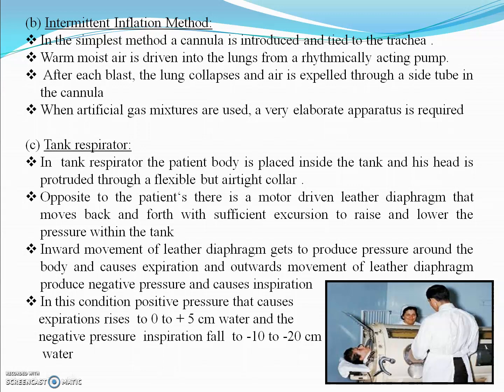Next is the tank respirator. In the tank respirator, the patient's body is placed inside the tank and his head protrudes through a flexible but airtight collar. Opposite the patient, there is a motor-driven leather diaphragm that moves back and forth with sufficient excursion to raise and lower the pressure within the tank. Inward movement of the leather diaphragm produces positive pressure around the body and causes expiration. Outward movement of the leather diaphragm produces negative pressure and causes inspiration.